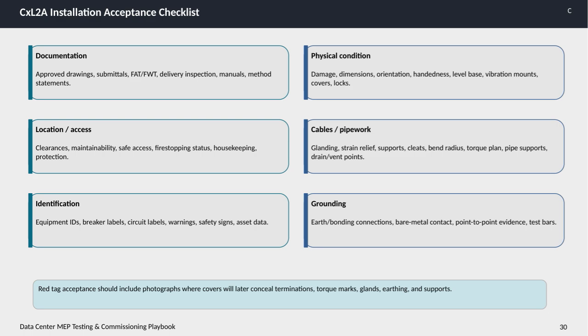When it comes to cables and pipework, the checklist covers glandings, strain reliefs, supports, cleats, bend radius compliance, torque plans, pipe supports, and proper drain and vent points. Correct installation here prevents future failures or maintenance issues. Identification is about labeling. Equipment IDs, breaker and circuit labels, warnings, safety signs, and asset data all need to be clear and accurate to support operation, maintenance, and safety protocols. Grounding checks focus on earth and bonding connections, ensuring bare metal contact is solid, confirming point-to-point continuity, and inspecting test bars. Proper grounding is critical for system safety and performance.